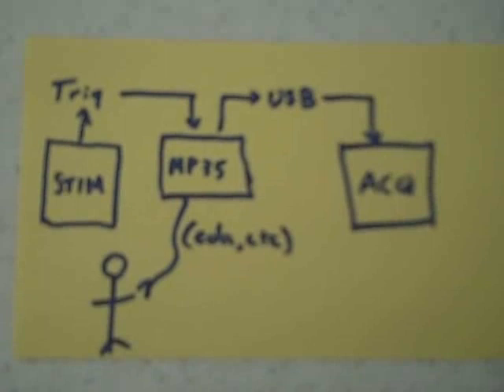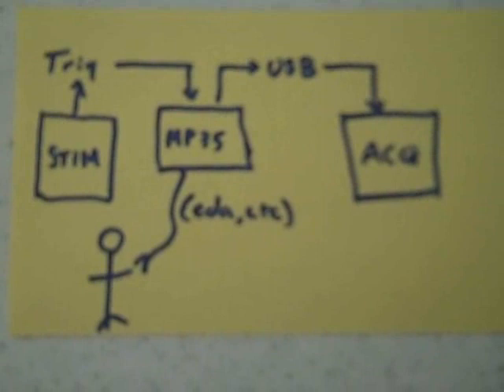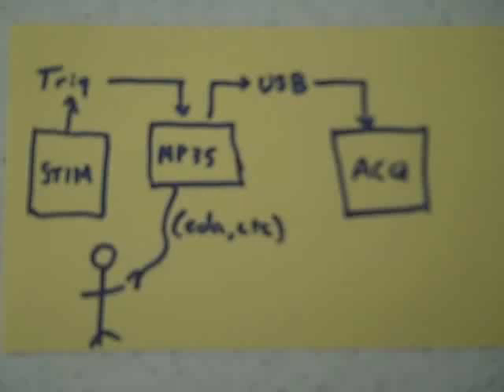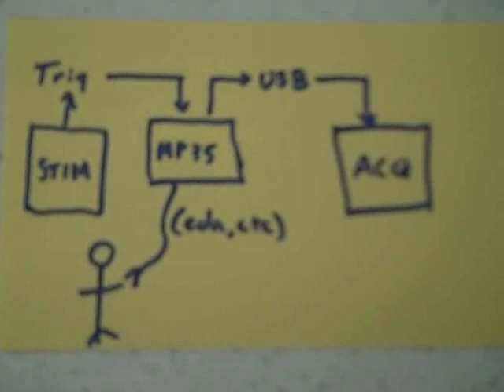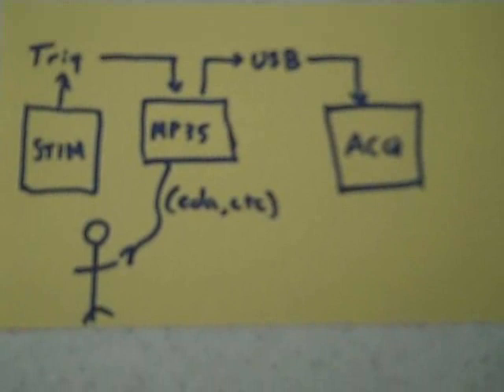While the MP35 is acquiring data through the EDA leads, it's also getting sent a trigger signal denoted by the arrows labeled Trig. That's fed out the back of the stimulus computer using the parallel port, then into the back of the MP35. We have a special connector cable for that. Once all of those data have been acquired and digitized by the MP35 unit, they're sent out through a USB cable to the acquisition computer, which runs separately in parallel to the stimulus computer, labeled ACQ on this diagram.